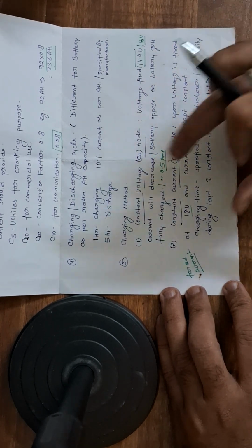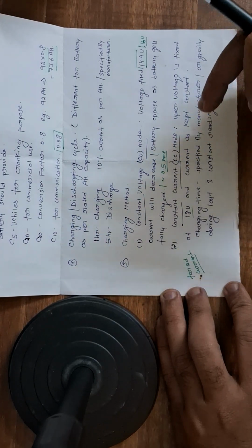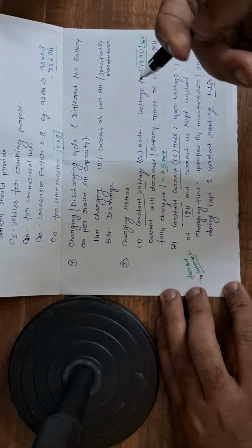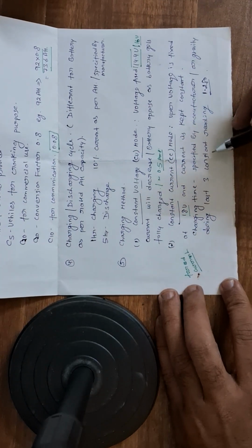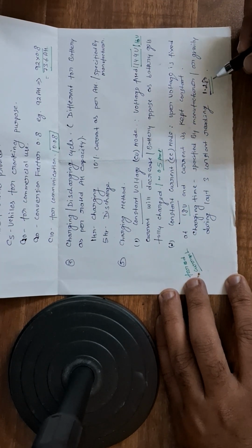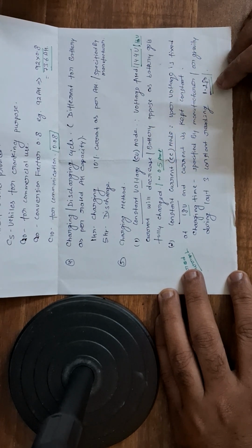Or if it is a standard lead acid battery, we have to check its gravity, meaning the electrolyte. For that, a gravity meter is there. During the last 3 cycles, a constant reading of 1.280 should be there. That means the battery is fully charged. When the gravity of the electrolyte becomes 1.280, it means the battery is fully charged.